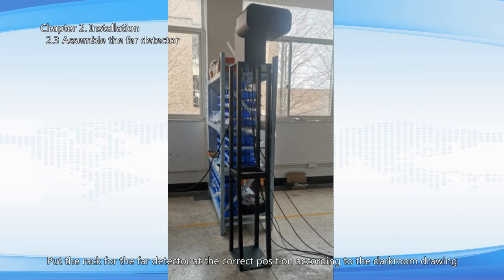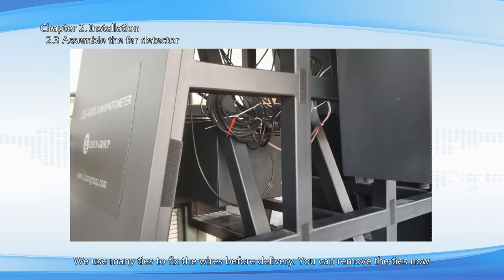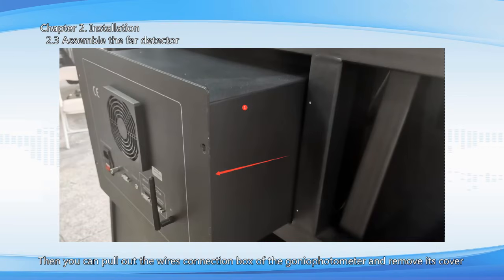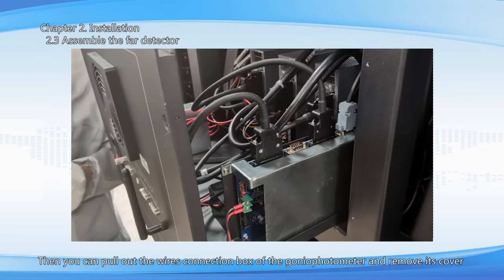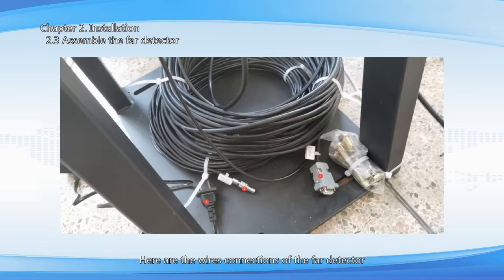Assemble the far detector. Put the rack for the far detector at the correct position according to the darkroom drawing. We use many ties to fix the wires before delivery. You can remove the ties now. Then you can pull out the wires connection box of the goniophotometer and remove its cover. Here are the wires connections of the far detector.